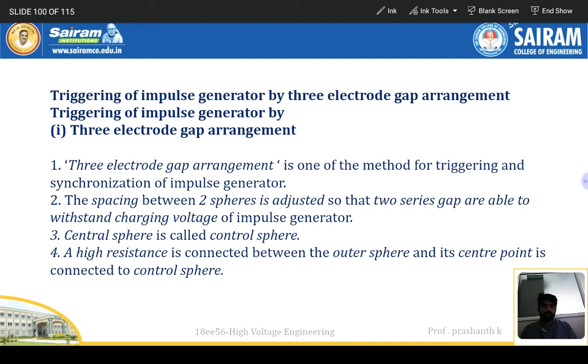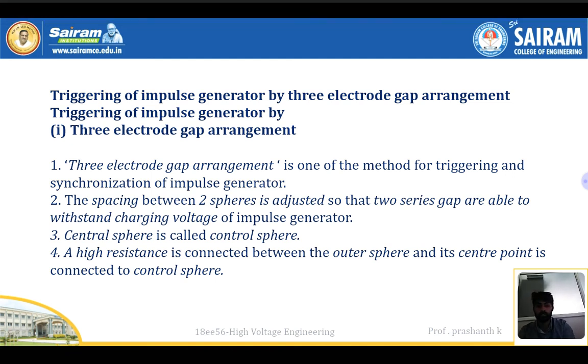The spacing between two spheres is adjusted. Two series gaps are able to withstand the charging voltage of the impulse generator. So for withstanding the charging voltage, and withstanding the high sparking or high flashover, we need to have this 3 electrode arrangement. The central sphere is called the control sphere. Of the spheres, we have a central sphere, that is the control sphere. A high resistance is connected between the outer spheres and its center point is connected to the control sphere.